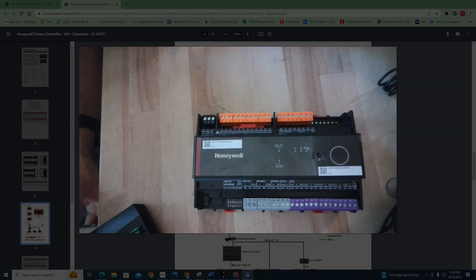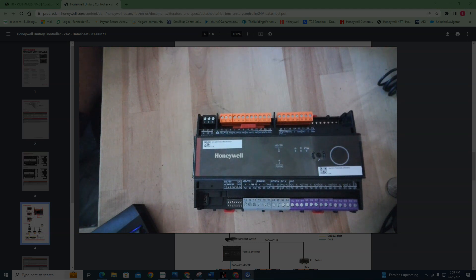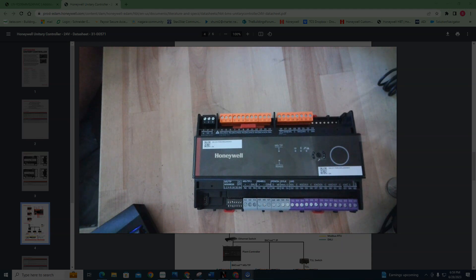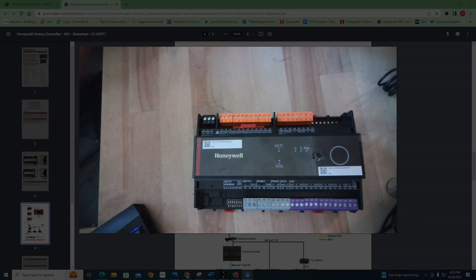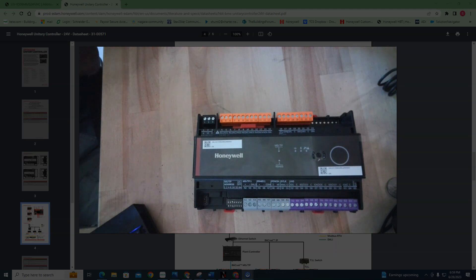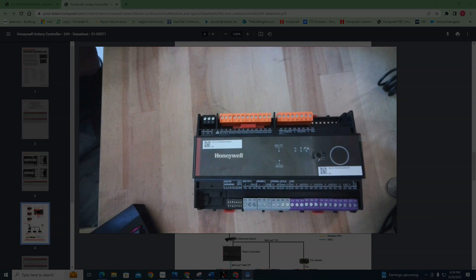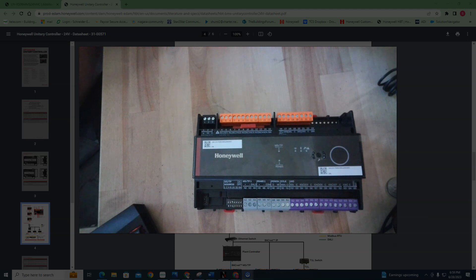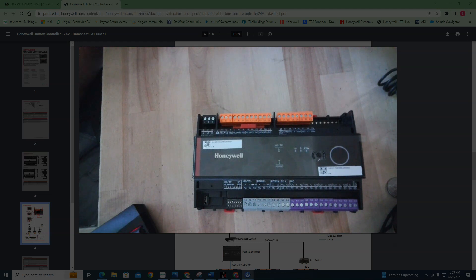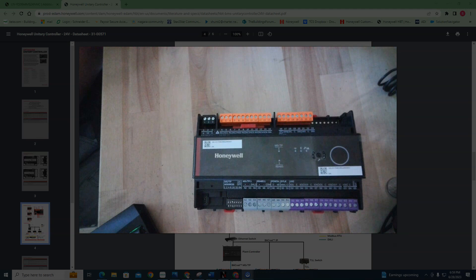Honeywell has some really cool sensors that are modbus now or modbus capable. You can use these IAQ sensors - they're basically TR50s. I'll do a video on those especially if I can get one in my hands soon. That TR50 can do VOCs, particulates, CO2, humidity, and temperature - up to five different things. They have a three version and five version. The three does CO2, humidity, and temperature, and these things are cheaper than TR42 HCO2, just so you know. The only drawback is they're just a sensor. You can get it with a display but there's no set point adjust on them, so you can use it to monitor a space but no set point adjustment at this time.